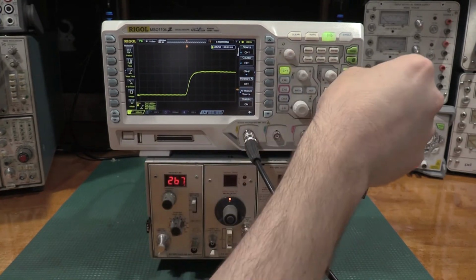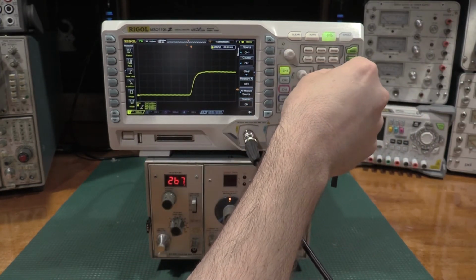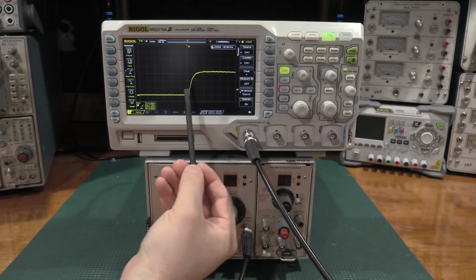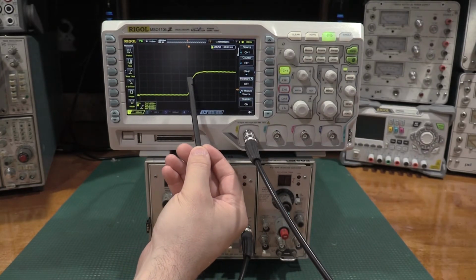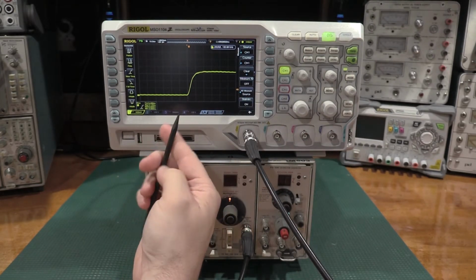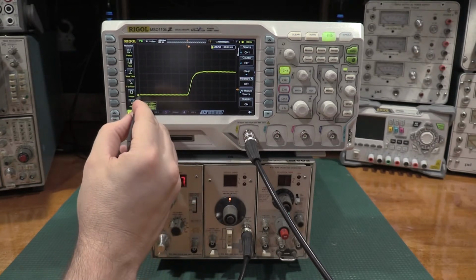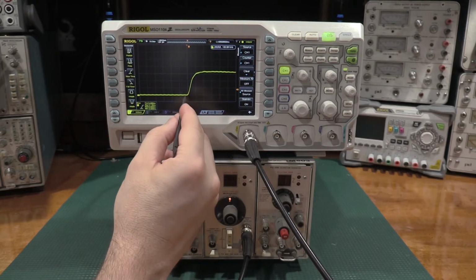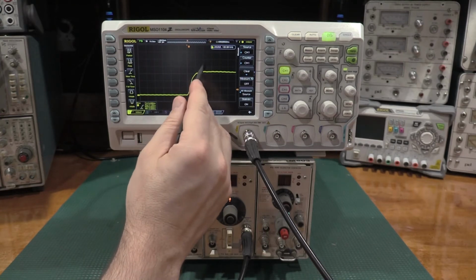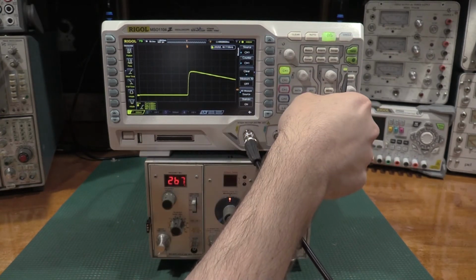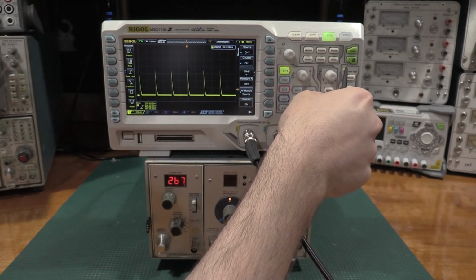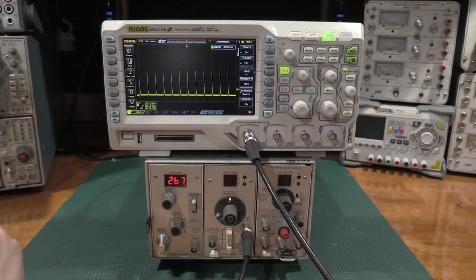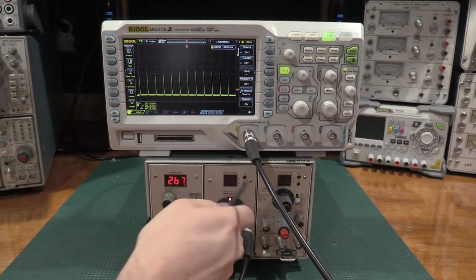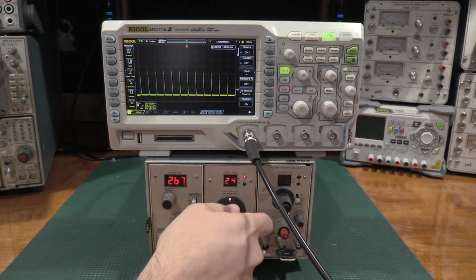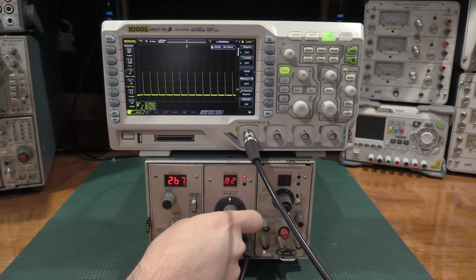So we have a pulse, a rise time pulse of less than 10 nanoseconds. So it's a very accurate period of a very sharp rise time pulse to allow you to align the horizontal of the scope. Really all it does, it makes time marks. Now what's one of the neat things about the TG is you can dial an error.